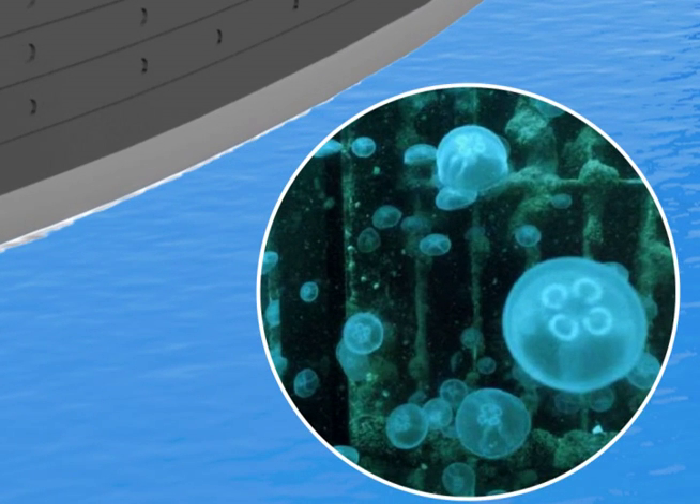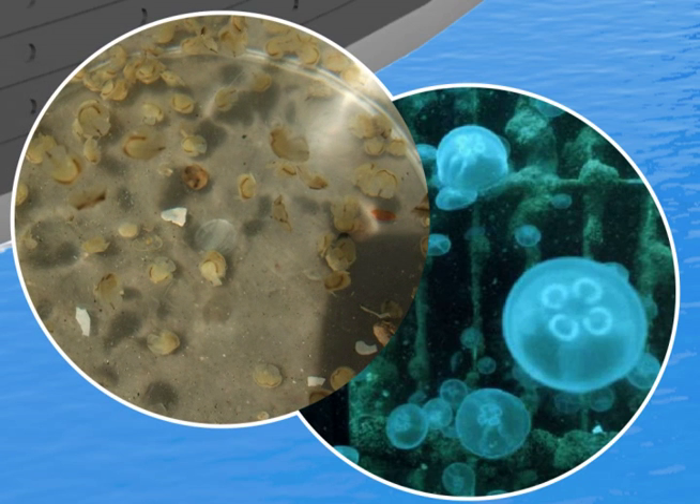This circulated seawater contains small sea creatures such as jellyfish that clog the straining filters of the cooling unit. Some of these small creatures manage to pass through the strainers and live and grow larger inside the cooling unit. This eventually leads to catastrophic failure of the equipment.